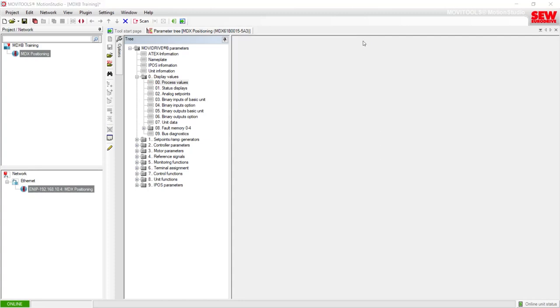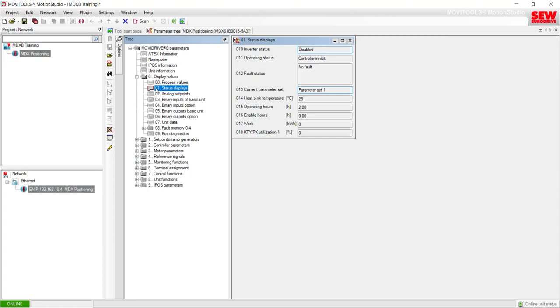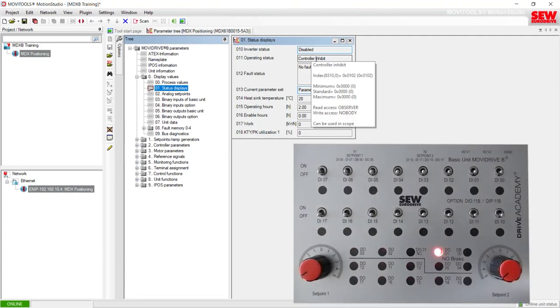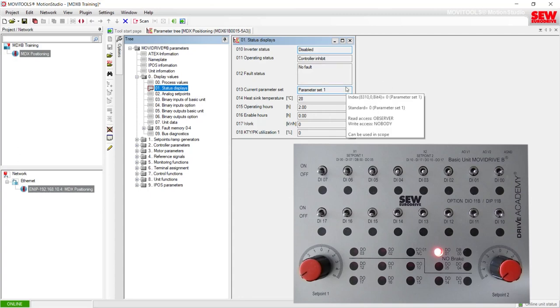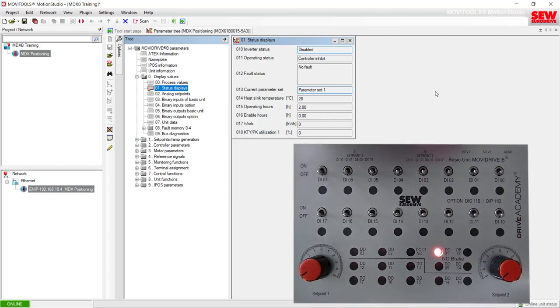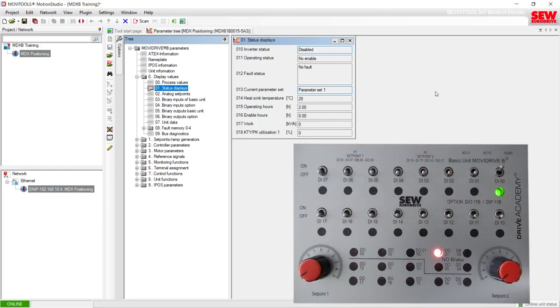The next question in the lab instructions asks what happens with the Status Display group. If we open up folder 01 Status Displays, you'll see the current inverter status is Disabled and it's currently Inhibited. One of the questions asks what happens when you flip the DI00 switch on the control box. I'll do that now — watch the inverter status and operating status for any changes. DI00 is now active. The inverter status stayed at Disabled but the operating status changed to No Enable.